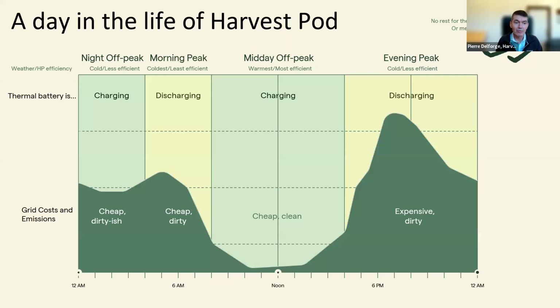And then at night, you may recharge the thermal storage if needed to top it up to be ready for the morning load. And then in the morning, you're going to start discharging the thermal battery again. So basically in the summer, when you have fairly limited thermal needs just for hot water, typically the heat pump will run maybe 2 hours in the middle of the day from 11 a.m. to 1 p.m. to charge on the cheapest, cleanest energy. And then you have enough hot water stored in the tank until the next day and repeat.